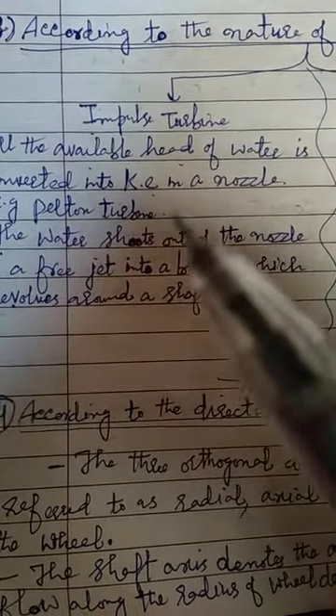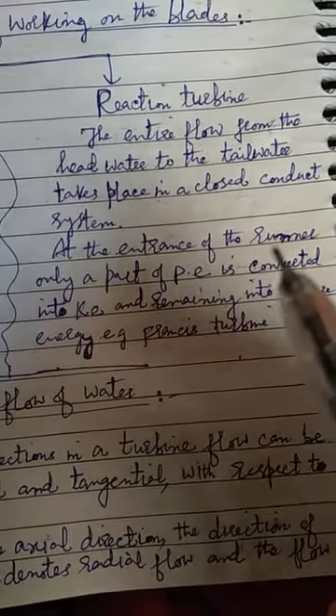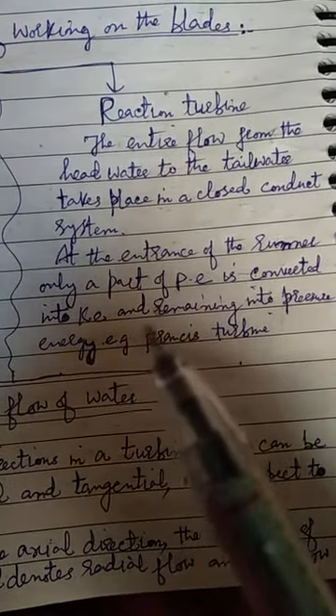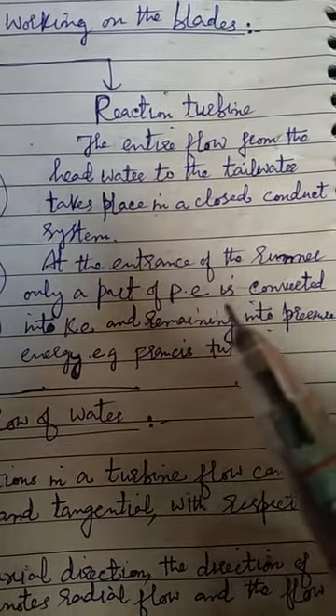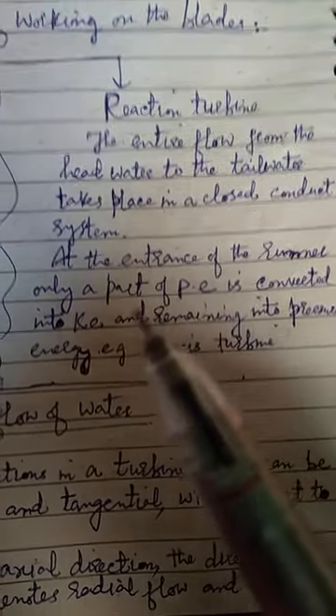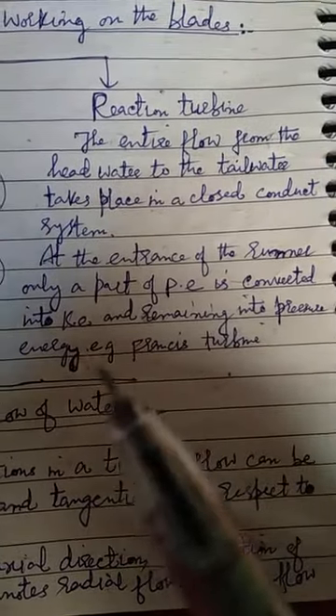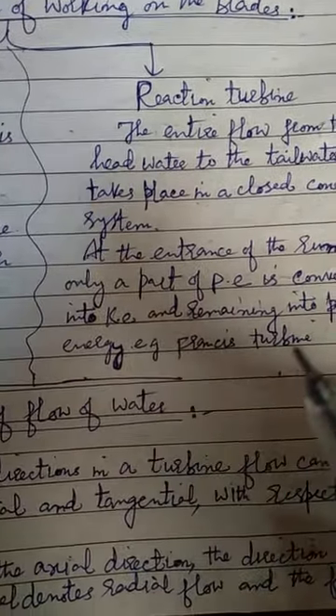The example of an impulse turbine is the Pelton turbine. For a reaction turbine, at the entrance of the runner, only part of the potential energy is converted into kinetic energy and the remaining part is converted into pressure energy — for example, the Francis turbine. So in reaction turbines, water energy is split into kinetic energy and pressure energy at the runner inlet, whereas in impulse turbines all energy is converted to kinetic energy at the nozzle.